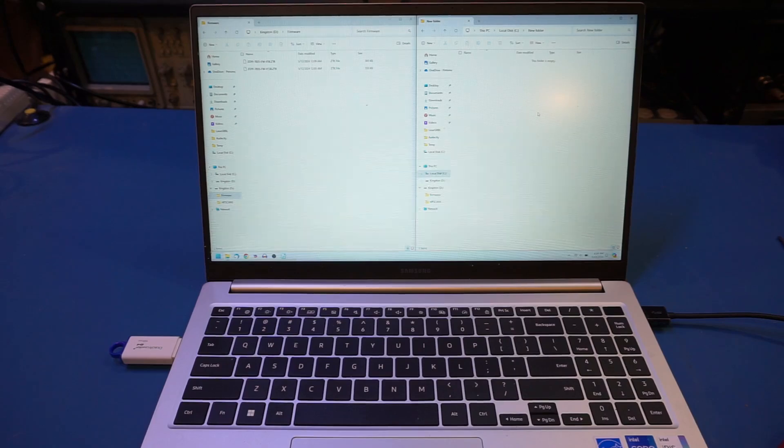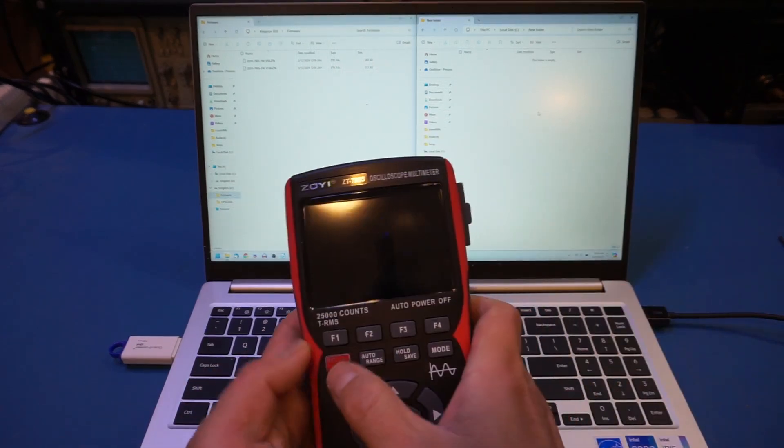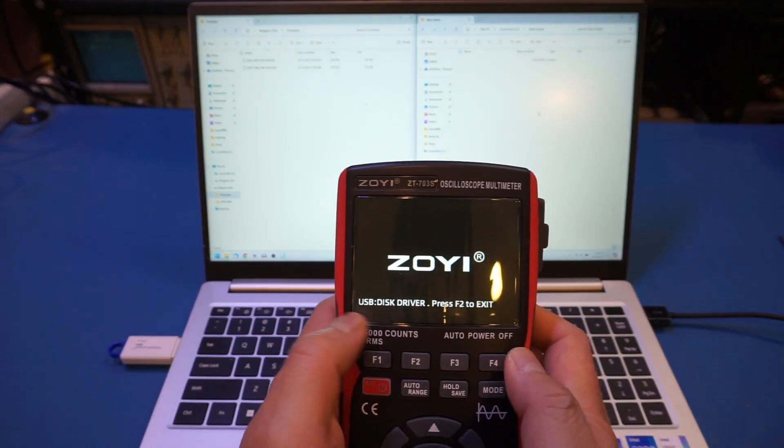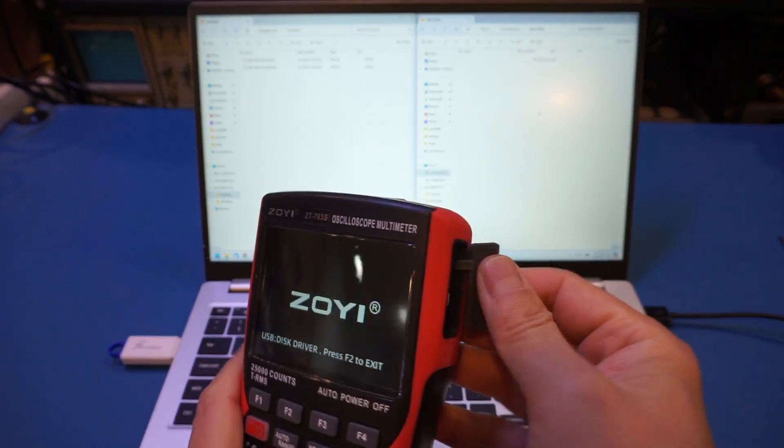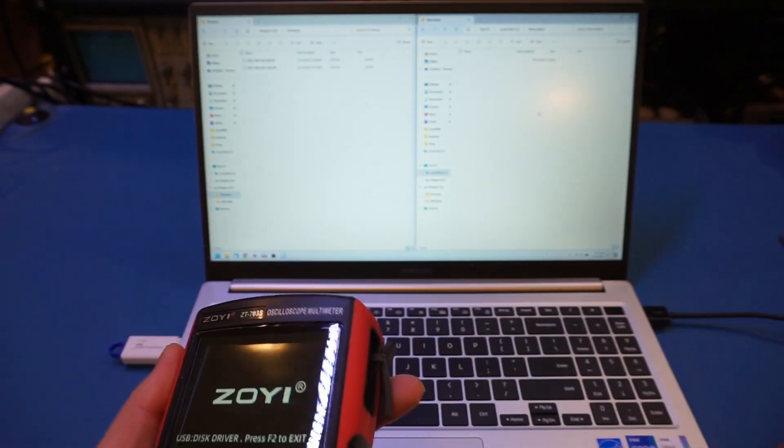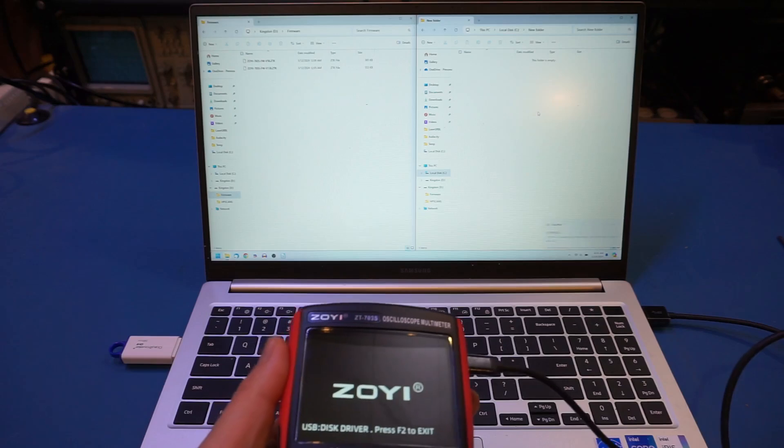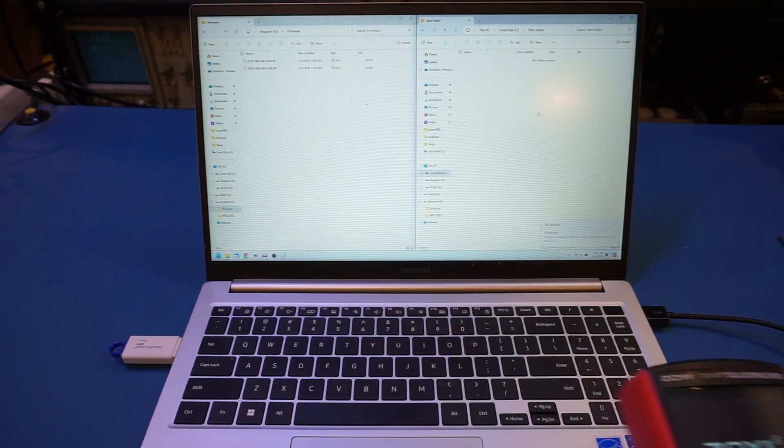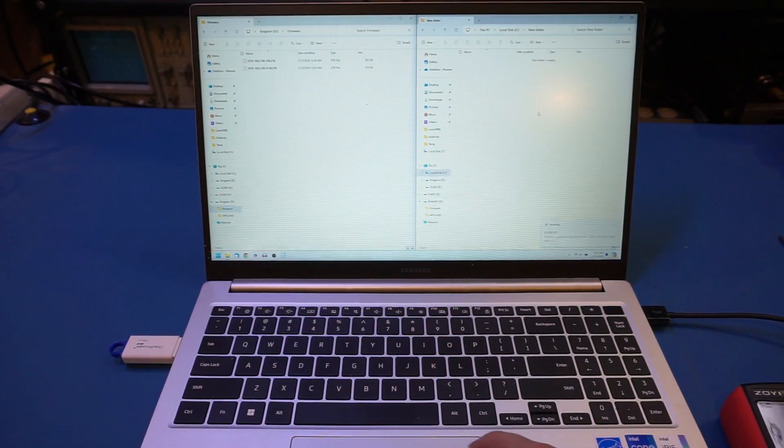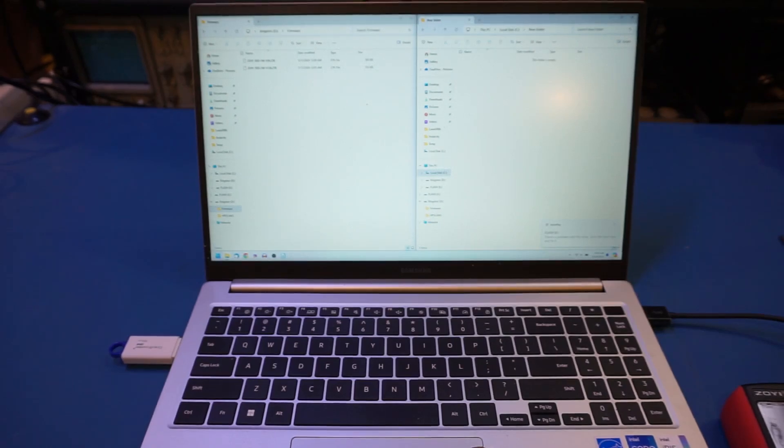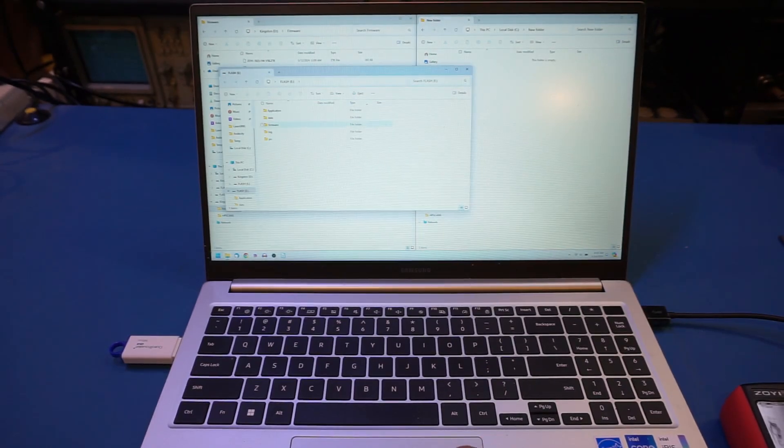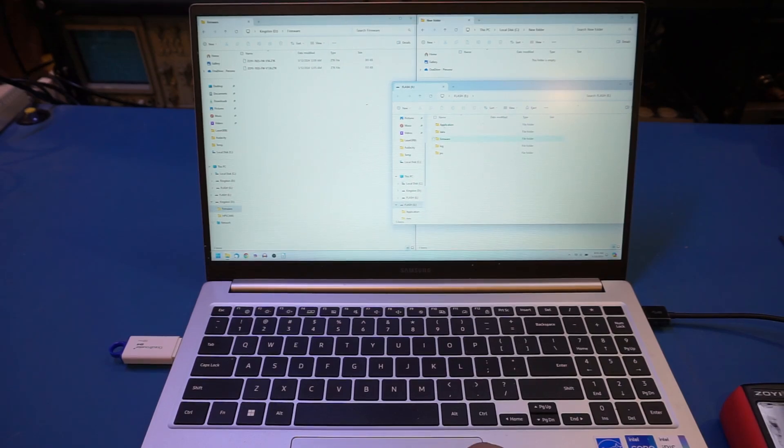All right, let's give it a try. According to the manual, I have to press both the F1 and power key together. Yep, and now we're in this disk driver mode. So hopefully we can just plug it in and it should recognize as a flash drive. And you can see we actually recognize it. So let me go here. I should be able to drag the firmware over to the firmware folder.